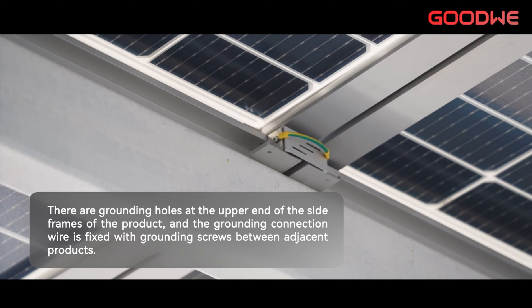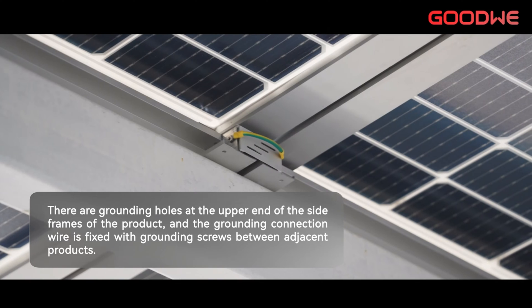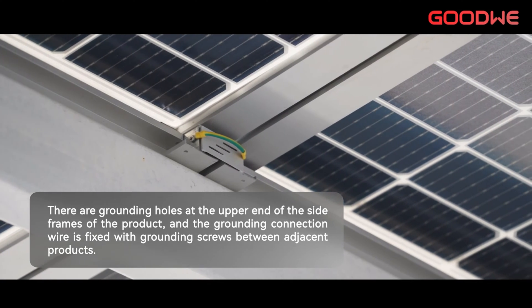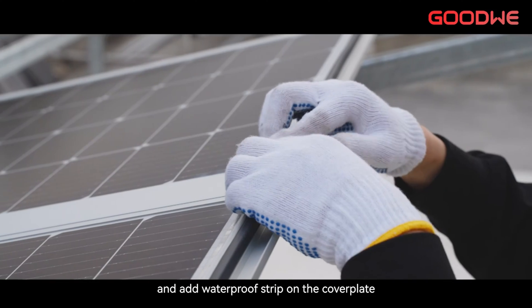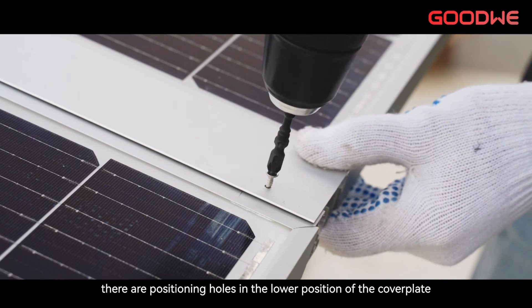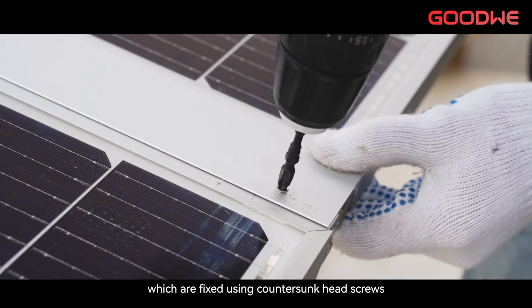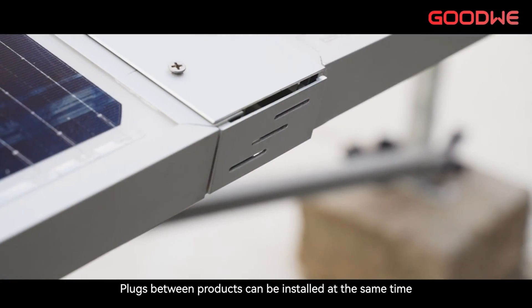There are grounding holes at the upper end of the side frames of the product, and grounding connection wire is fixed with grounding screws between adjacent products. Install the cover plate between the two pieces of product with a waterproof strip on the cover plate. To prevent the cover plate from slipping, there are positioning holes in the lower position of the cover plate, which are fixed using countersunk head screws. Plugs between products can be installed at the same time.